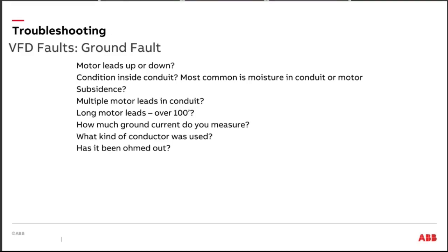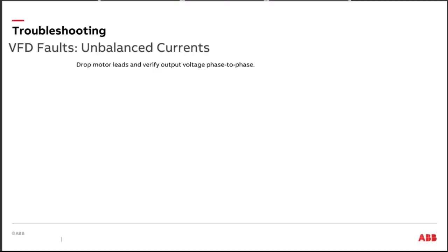And friends, let me tell you something. If that drive goes down on ground fault, don't waste your time troubleshooting that drive. You start looking from that motor lead out, because a drive, if it can't do anything, it can do a fabulous job for ground fault. So if you're getting a ground fault trip, don't start by looking at the drive. You start on that motor lead out to the field, not the drive itself. That'll save you a lot of time.